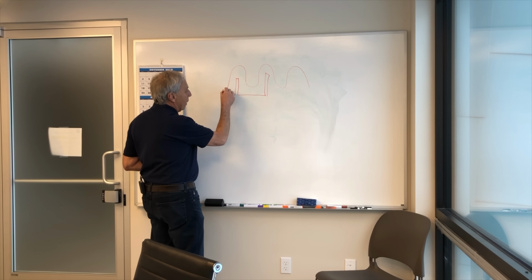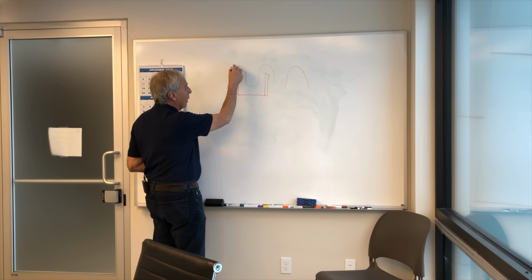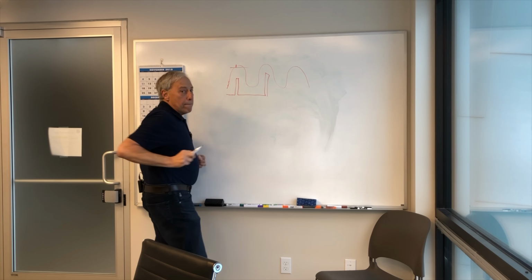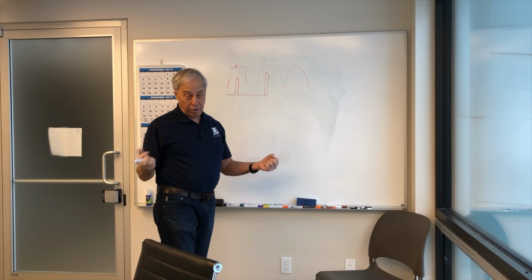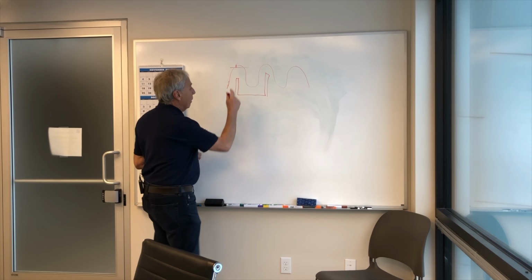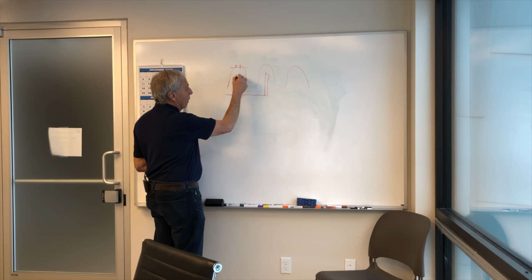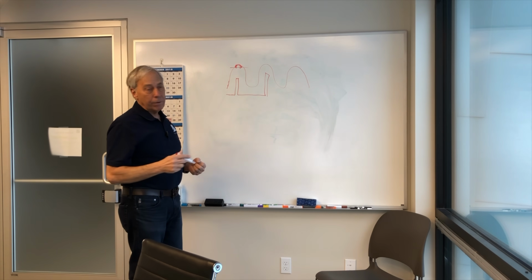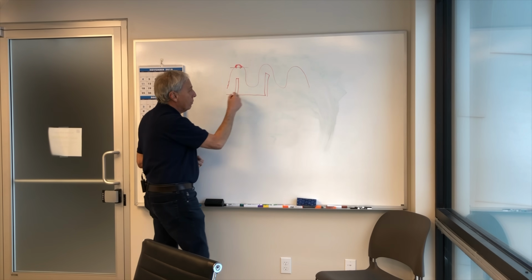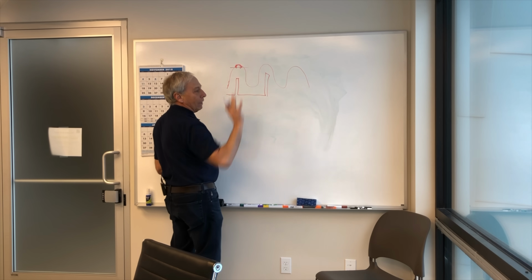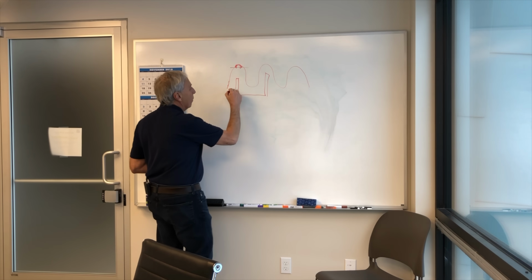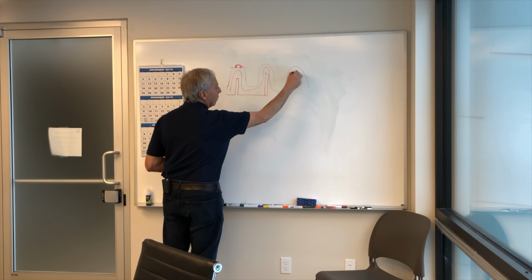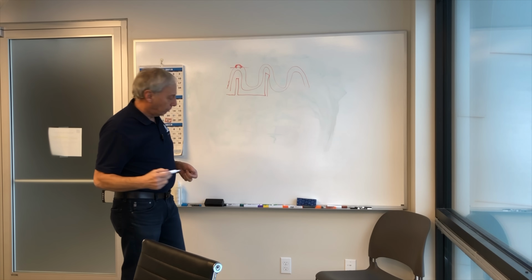So as the voltage goes in and rises, no current's being drawn. And when it gets right up to here, at this point, all of a sudden, bam, all kinds of current are being drawn, okay? And that's where this big spike of current comes, and then we're just filling in this little part up here. That's all we're doing. The rest of this is not drawing any current. And so you get this pulse of current that doesn't match this beautiful current of a power factor of 1.